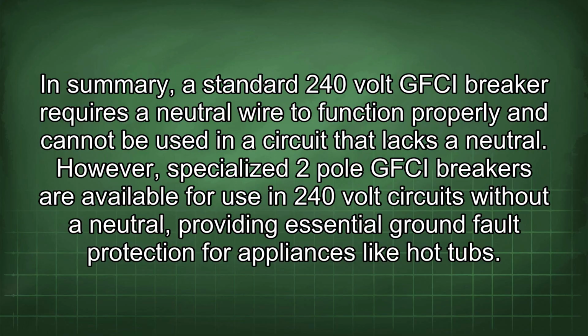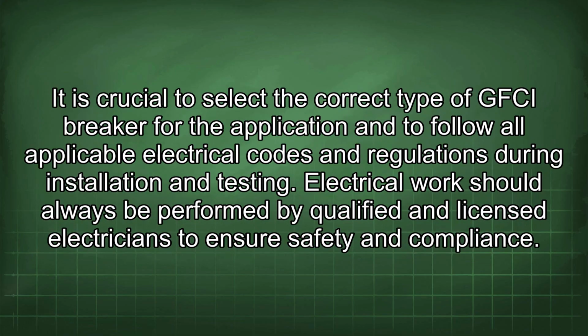However, specialized 2-pole GFCI breakers are available for use in 240-volt circuits without a neutral, providing essential ground fault protection for appliances like hot tubs. It is crucial to select the correct type of GFCI breaker for the application and to follow all applicable electrical codes and regulations during installation and testing. Electrical work should always be performed by qualified and licensed electricians to ensure safety and compliance.